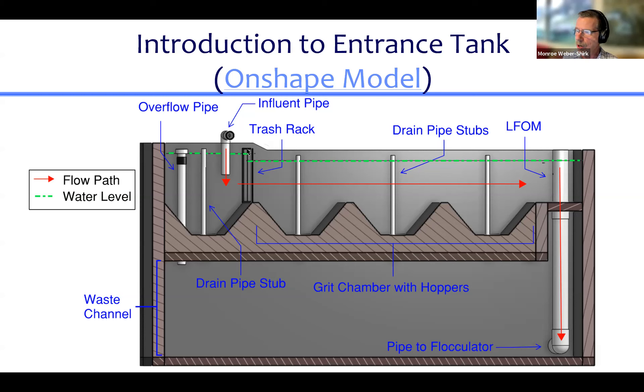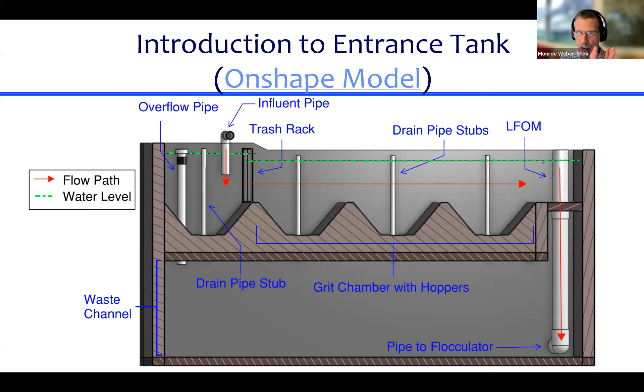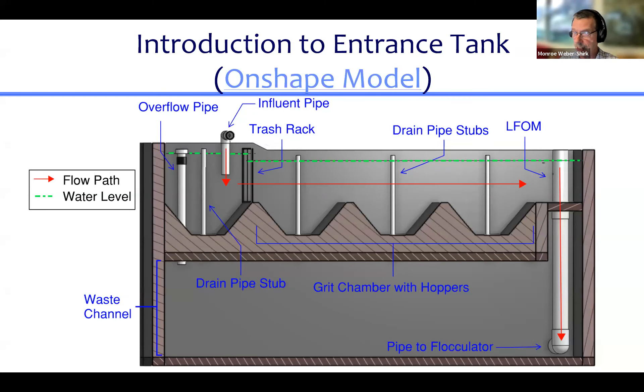The green line shows the water level, and there's going to be a drop in water elevation as it goes through the trash rack - that's called head loss. There's a drop in energy because we're using energy to push the water through the trash rack. The trash rack helps us remove large particles, debris, twigs, and even small branches, depending on how big the pipeline is, protecting the rest of the plant.